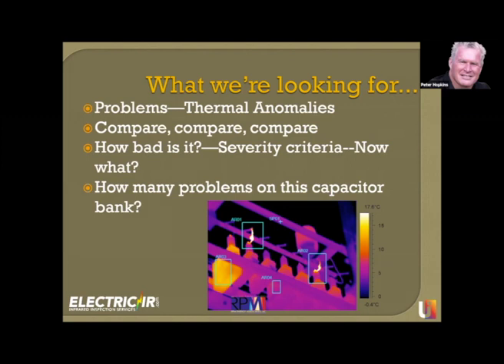Once you find a problem, you have to determine how bad it is. There are criteria tables out there — we use a guideline called EPRI, and there's an NFPA guideline in 70B that tells you certain temperature requirements. Once you know that, along with some idea of the load, you can make a decision just by looking at these pictures.